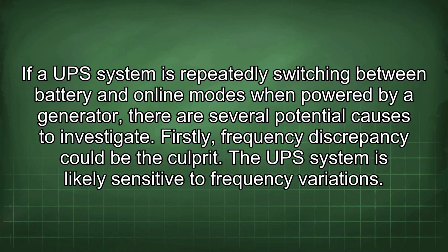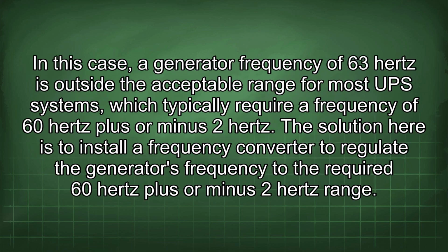If a UPS system is repeatedly switching between battery and online modes when powered by a generator, there are several potential causes to investigate. Firstly, frequency discrepancy could be the culprit. The UPS system is likely sensitive to frequency variations. In this case, a generator frequency of 63 Hz is outside the acceptable range for most UPS systems, which typically require a frequency of 60 Hz plus or minus 2 Hz. The solution here is to install a frequency converter to regulate the generator's frequency to the required 60 Hz plus or minus 2 Hz range.